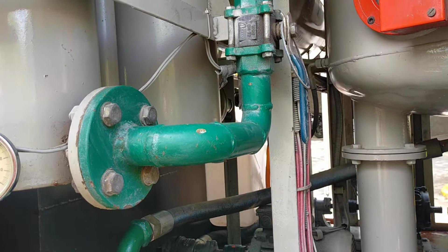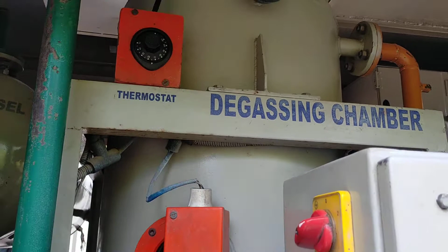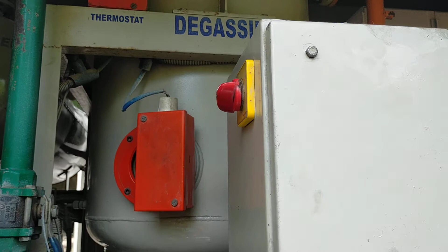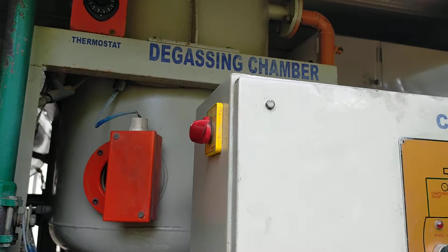And after heating the oil up to 60-70 degrees Celsius, it comes to the fine filter. In this fine filter, it will be filtered once again and it goes to the pre-filter. Okay, this is the fine filter and this is the pre-filter. After completion of the filtration, it will go to the degassing chamber. This tank, the big tank you are seeing, is the degassing chamber. There, whatever moisture and gases are present in the oil will be separated.